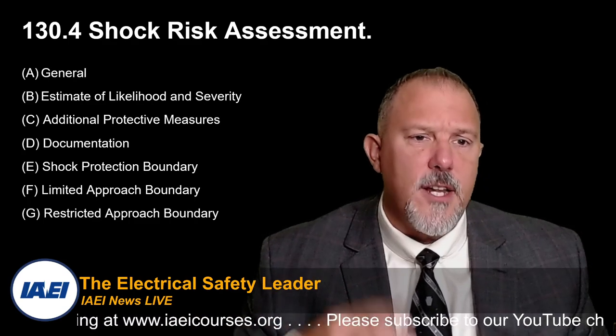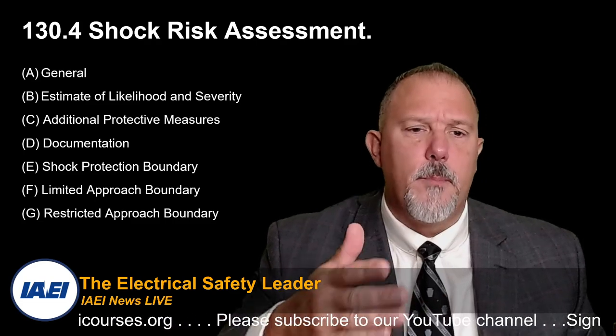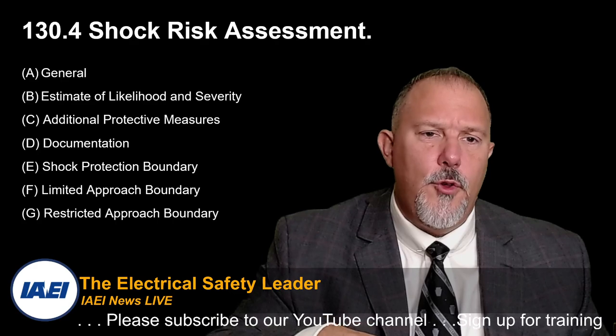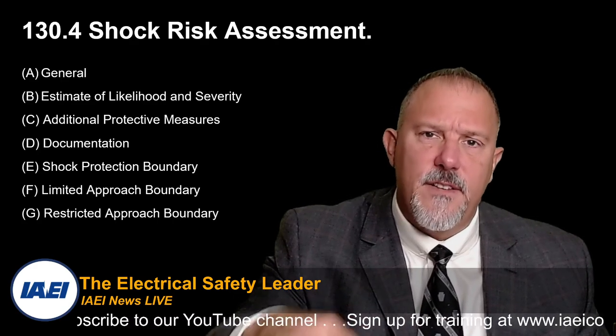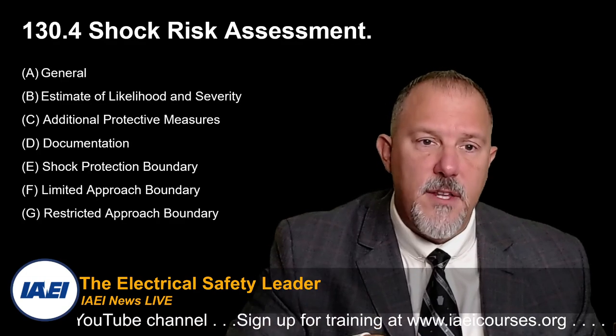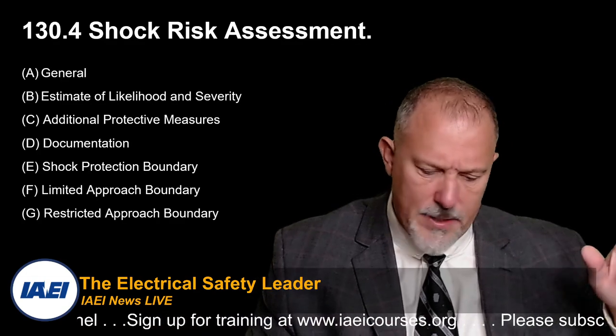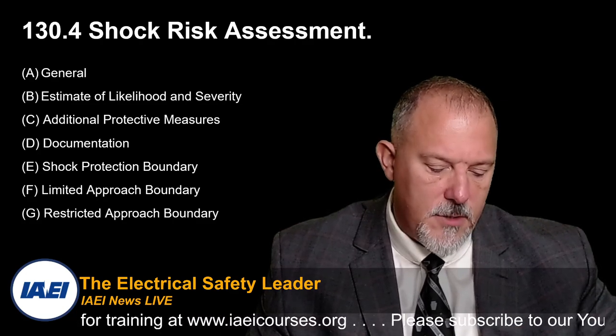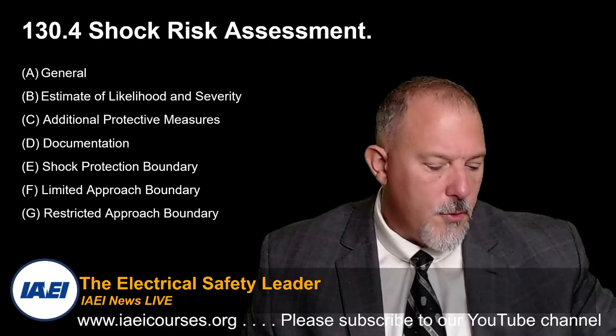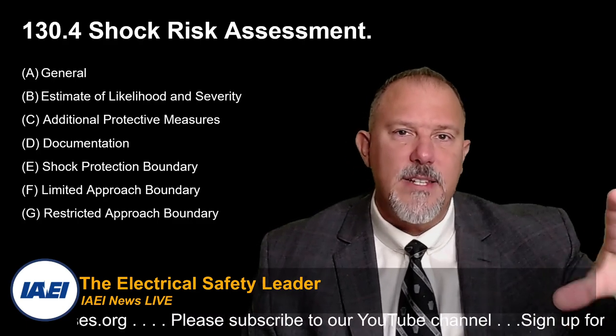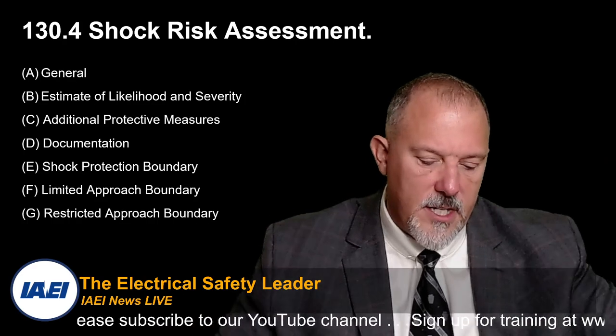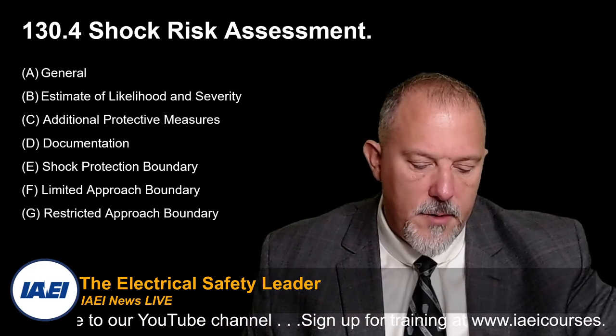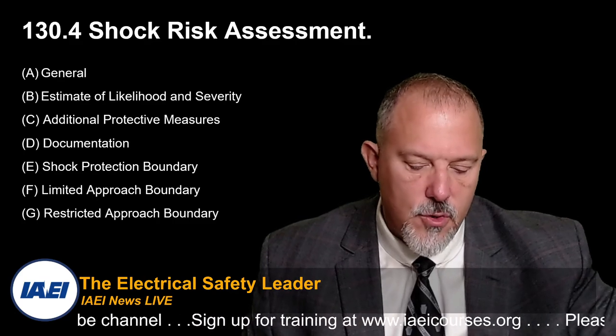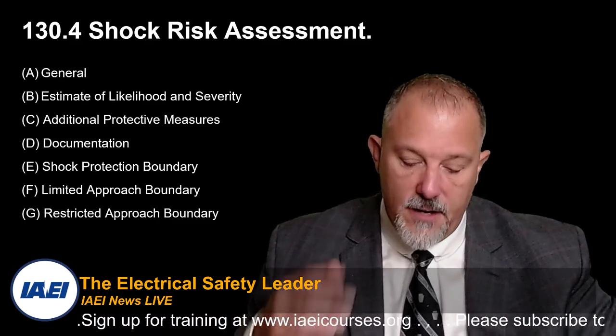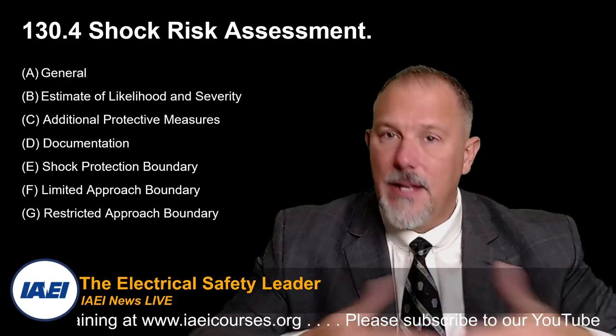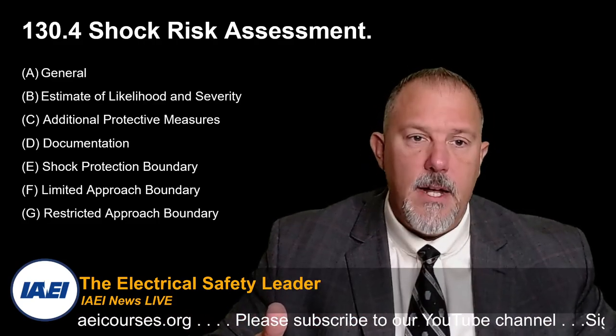Additional protective measures, documentation, shock protection boundaries. What are our limited approach boundaries? So you have to be able to estimate the likelihood and severity of shock. You have to provide methods for protection. You have to document. Let's take a look at what documentation is. The results of the shock risk assessment shall be documented. So you're going to identify the hazard. You're going to estimate likelihood and severity. You're going to look at what the additional protective measures are. If additional protective measures are required, they shall be selected and implemented in accordance with the hierarchy of risk control identified in 110.5H3. Hierarchy of risk control is all about trying to eliminate the hazards, et cetera. And then you have your documentation.